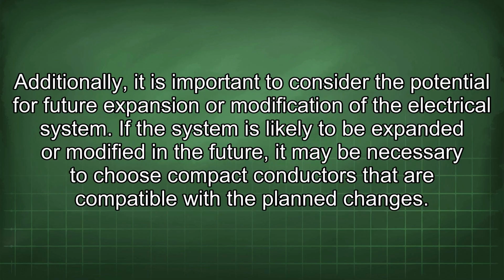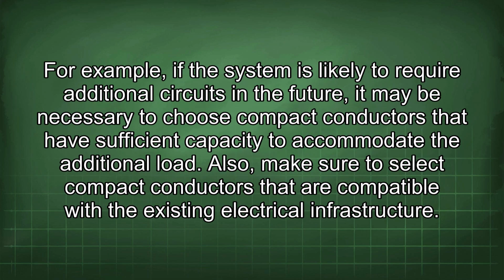Additionally, it is important to consider the potential for future expansion or modification of the electrical system. If the system is likely to be expanded or modified in the future, it may be necessary to choose compact conductors that are compatible with the planned changes. For example, if the system is likely to require additional circuits in the future, it may be necessary to choose compact conductors that have sufficient capacity to accommodate the additional load.